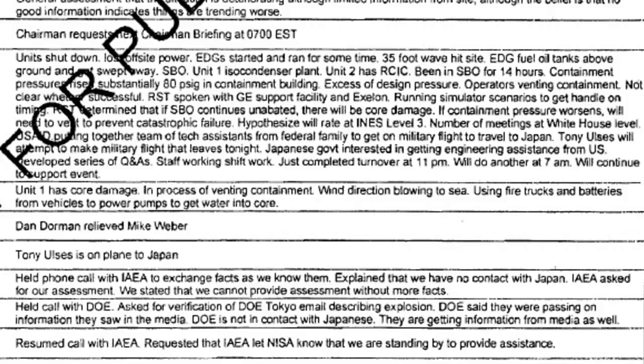Running simulator scenarios to get a handle on the timing, to determine that if the SBO continues unabated, there will be core damage. If containment pressure worsens, we'll need to vent to prevent catastrophic failure. Hypothesize this will rate an INES level 3.